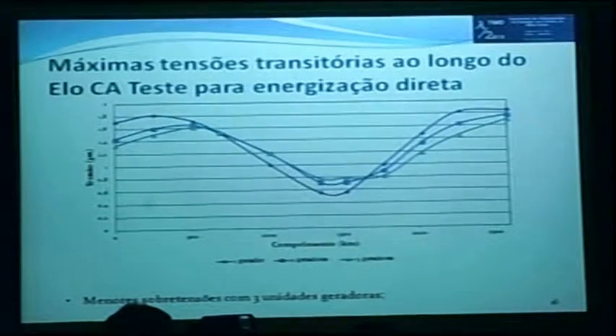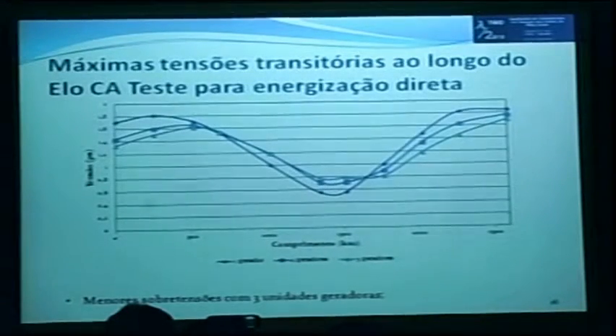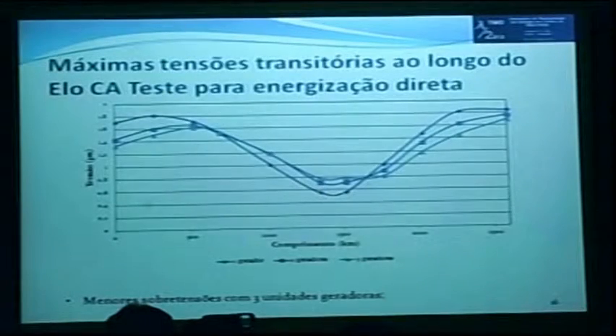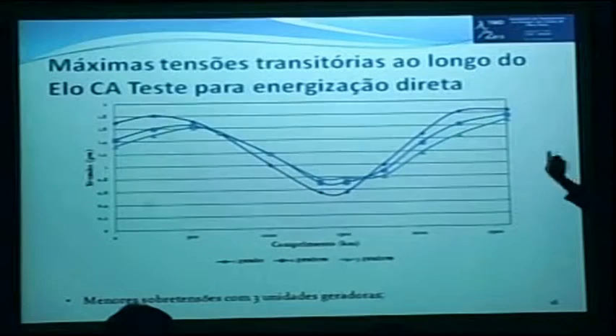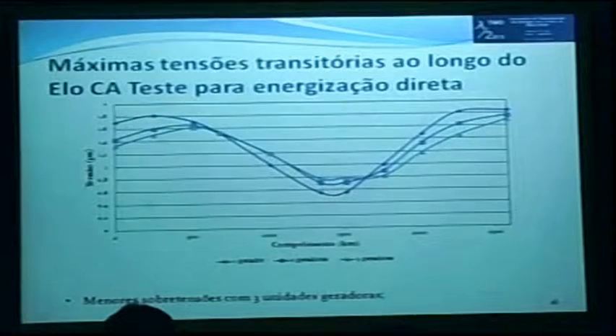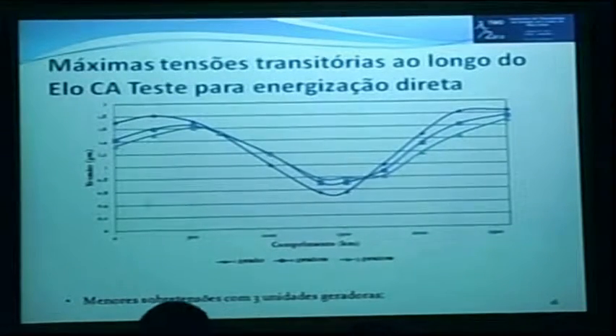In the transient study, we reached 1.9 pu, which is not a high disturbance. We are energizing a line of 2,600 kilometers with a single generator of 475 MVA, and the overvoltage I had at the end was 1.90 pu, which would be the overvoltage without any method; it was energized at once. So why not use pre-insertion circuit breakers? It's something that, when we start working with half wavelength, we do not expect such a low overvoltage.